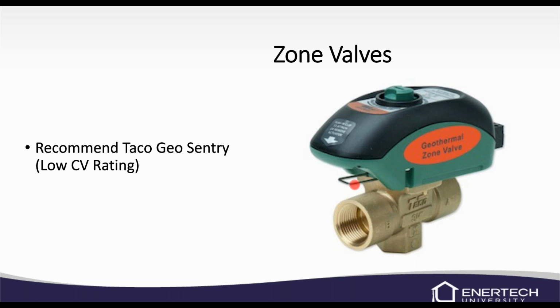You can remove this head. You got to pull on this little metal tab, and it'll come right off. You can also manually open these valves and leave them open for flushing and that kind of thing. Again, super reliable, a lot better than the orange-headed Taco zone valves that we used to use back in the day. We've been using these for a long time now. So this is what I would recommend on your zoning, is the Geo Sentry valve.